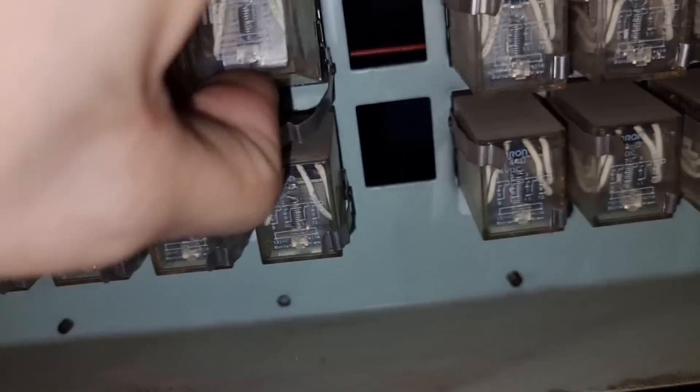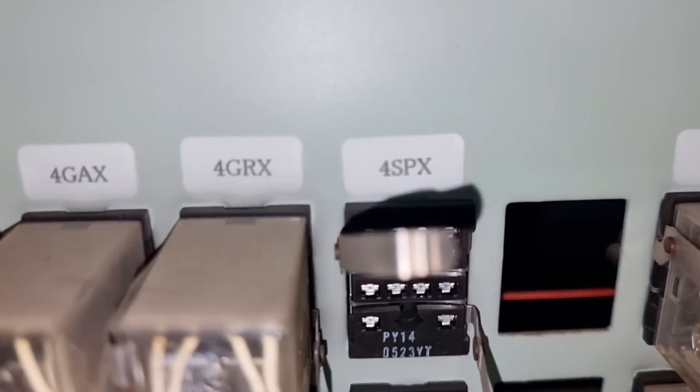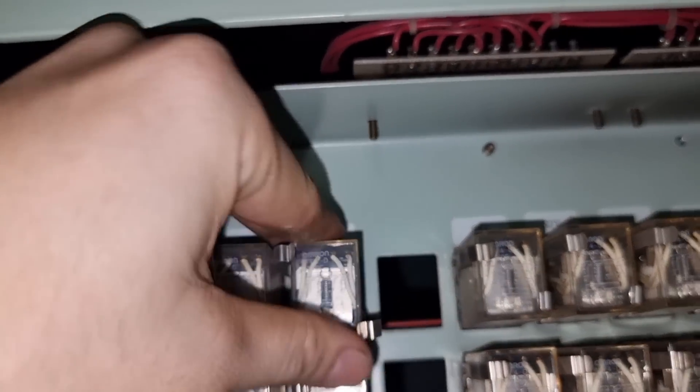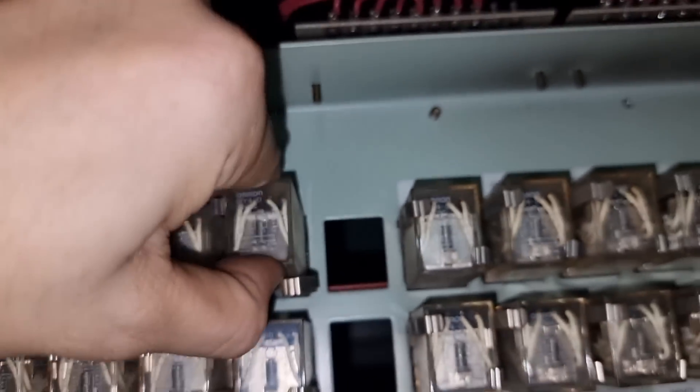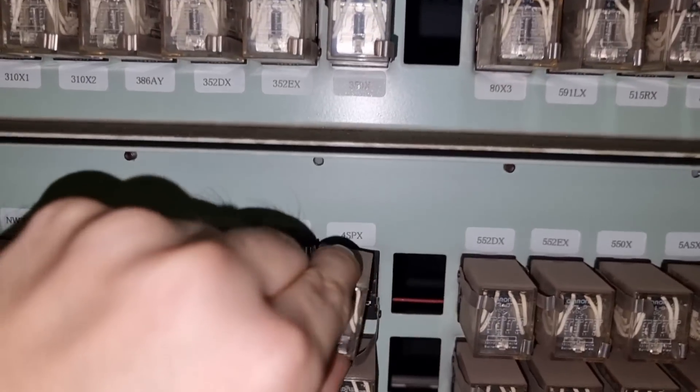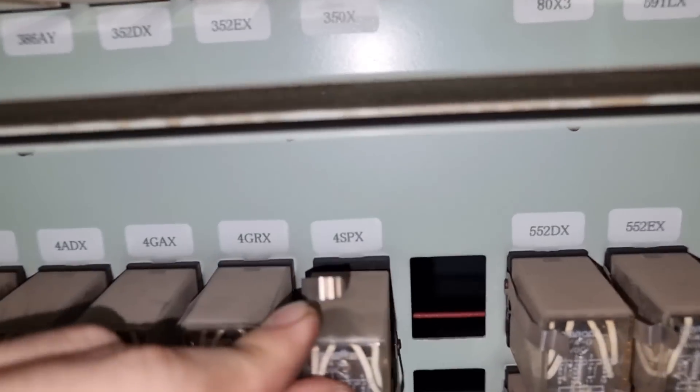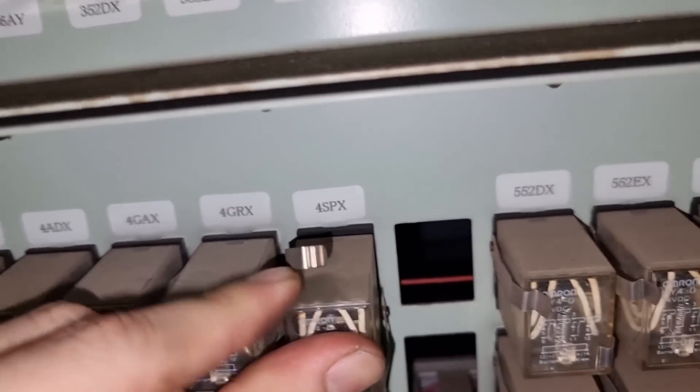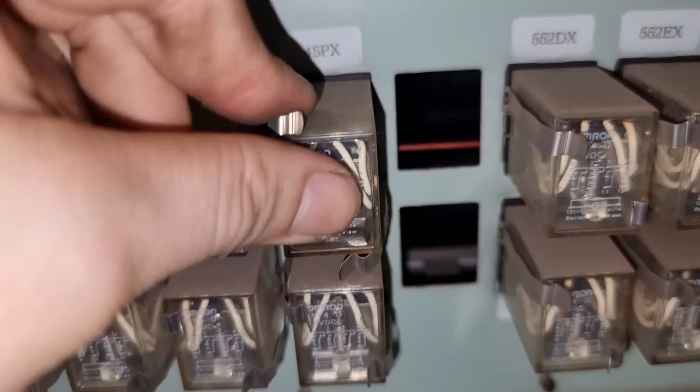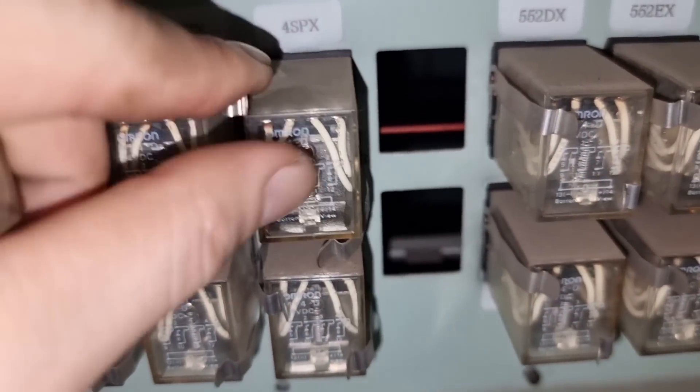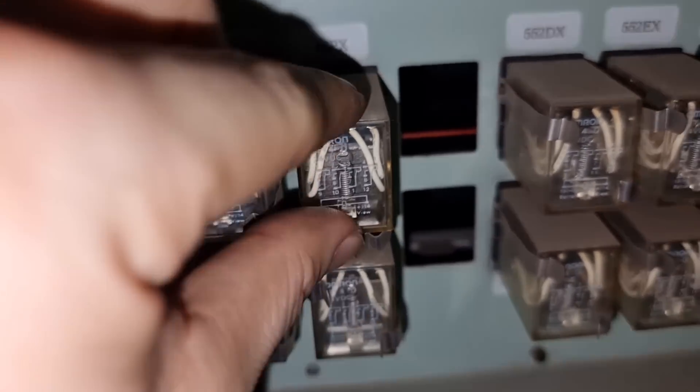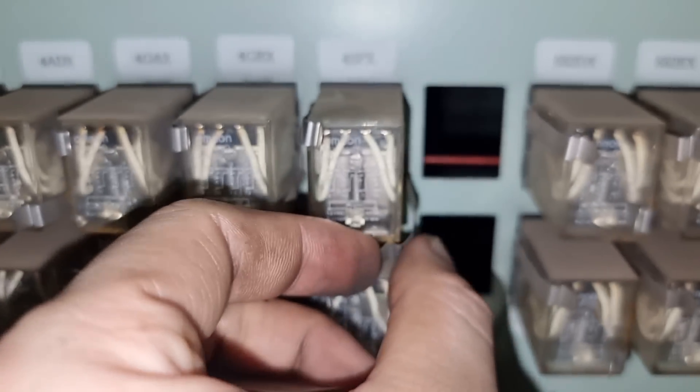To ensure also that we have a good contacts onto our 4SPX, I also interchanged this relay onto our number 1 generator. This generator number 1 is not running. So just to be sure that we have a good condition on the contacts. And then we will measure again the supply voltage on this relay if we are getting 24 volts.